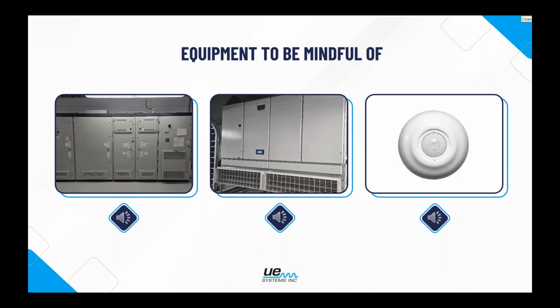The first example I have on the left is the VFD station. This will always create a high pitch ultrasonic frequency. So just be aware that it's a natural harmonic of this equipment from the nature of it, but it can reflect off of other pieces of equipment. So do the visual inspection before you start sweeping the area.